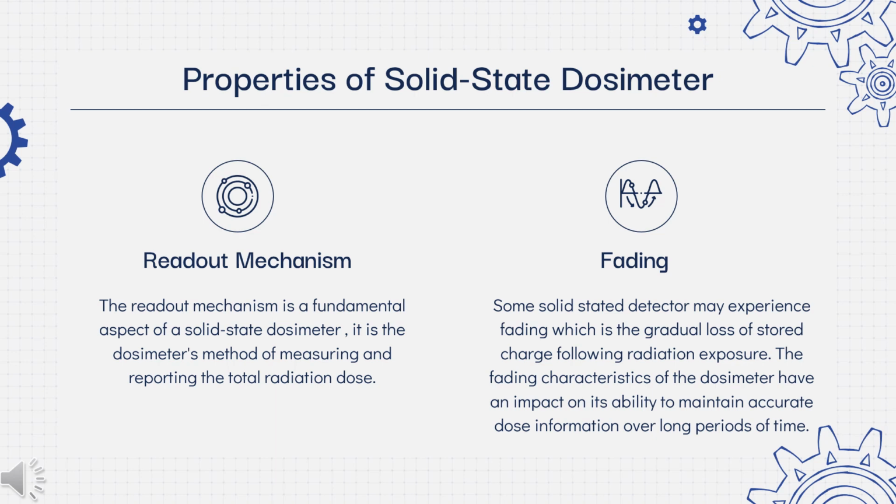Fading is often more pronounced in TLD. Fading in TLD can be influenced by many factors such as the temperature, storage conditions, and the characteristics of the specific dosimeter material.